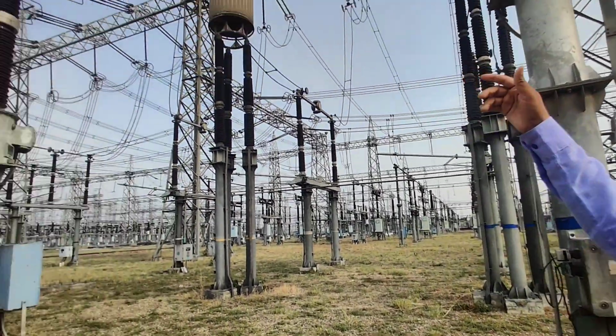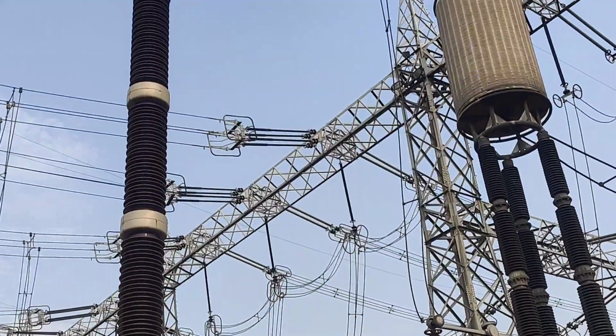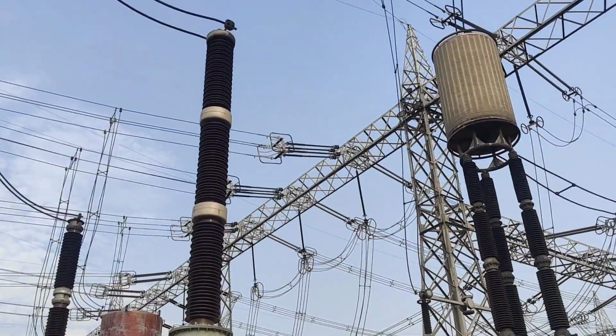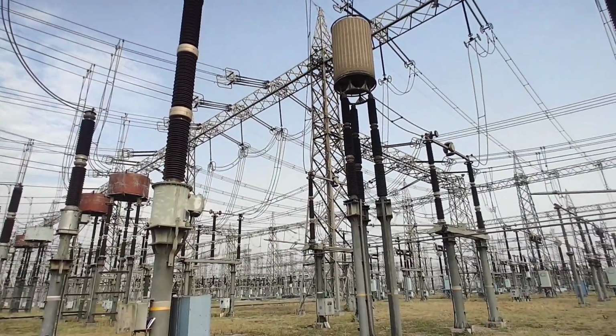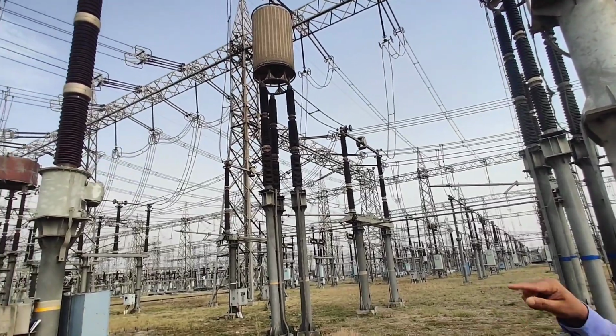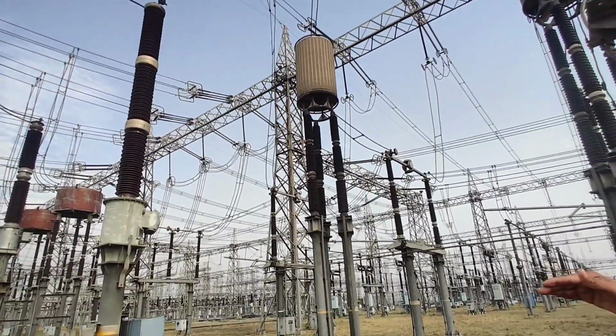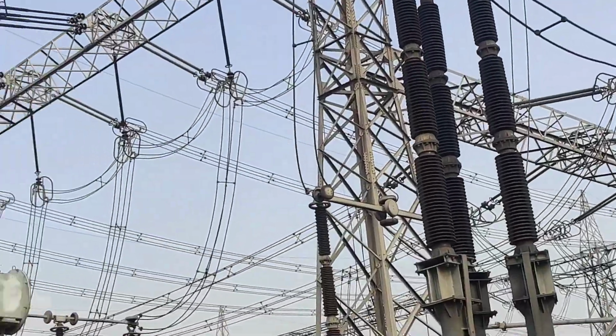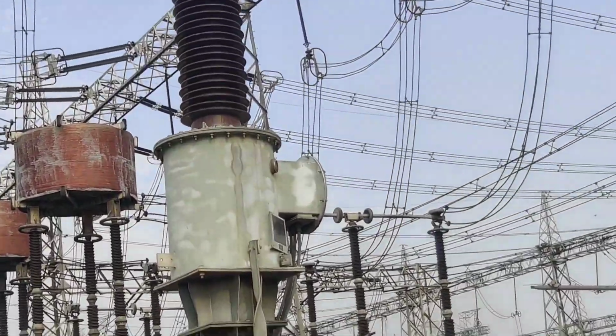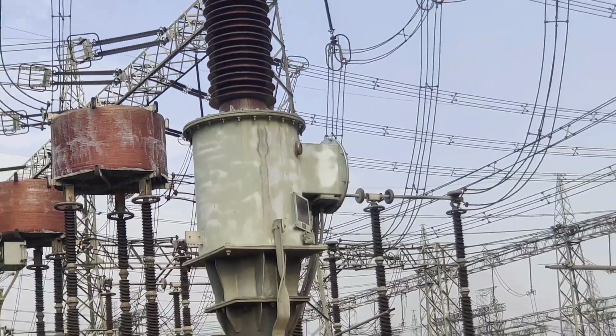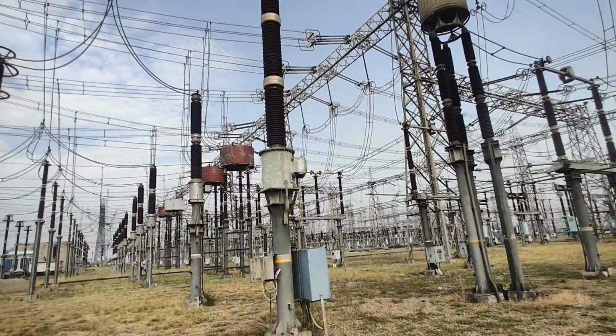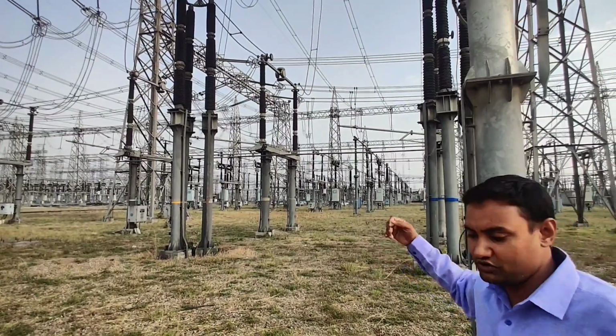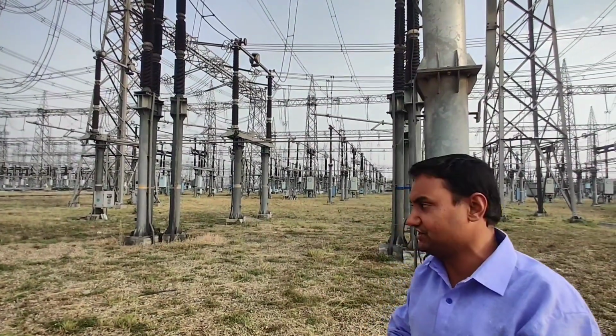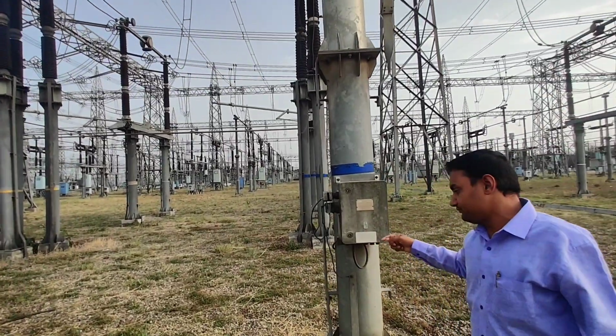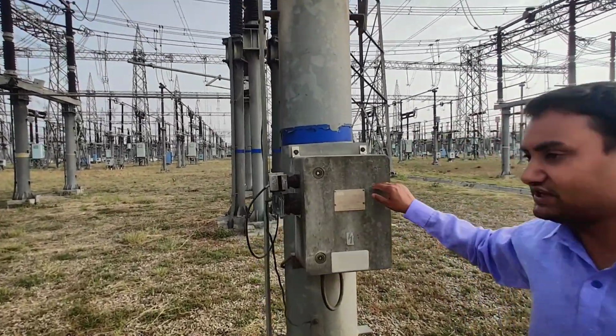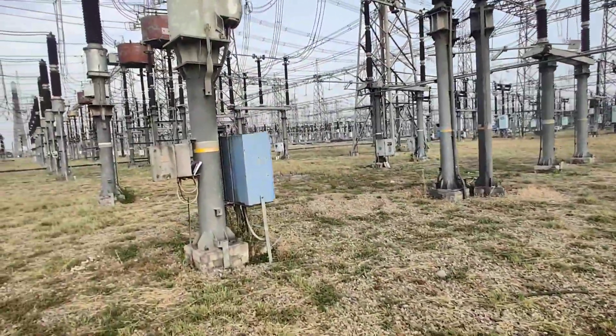So if you see here this CVT, there are 3 stacks, and inside these 3 or 2 whatever stacks, there are the capacitor units, and those capacitor units are used for dropping that 400 kV to a lower voltage of 33 kV. In the lowermost side you see there is a circular or cylindrical dome. In this cylindrical dome there is a potential transformer which reduces that 33 kV voltage level to 110 volt for your protection and measuring devices. The next element that is inside this is your line matching unit or LMU.